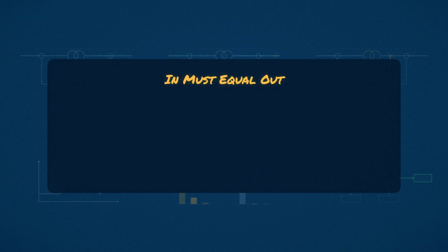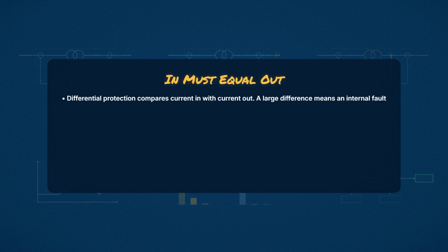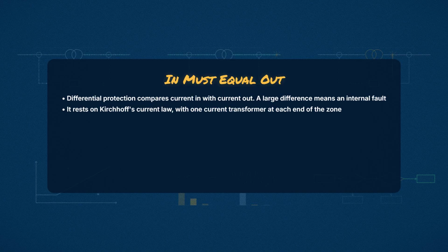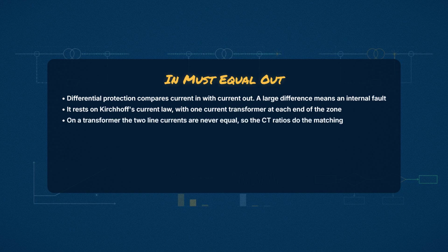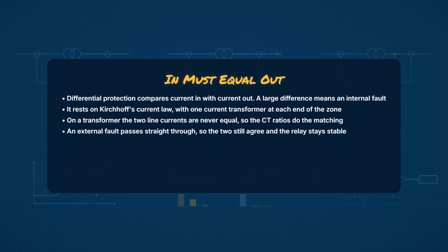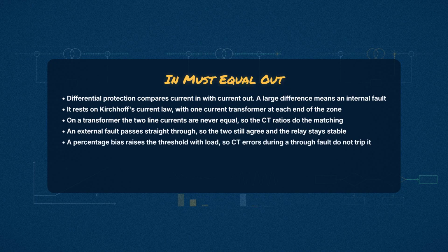So, a recap. Differential protection compares the current going in with the current coming out. A large difference means an internal fault. It rests on Kirchhoff's current law, using one current transformer at each end of the protected zone. On a transformer, the two line currents are never equal, so the current transformer ratios do the matching, and the relay compares what they hand it. An external fault passes through the zone, so the two still agree, and the relay stays stable. A percentage bias raises the trip threshold as the through current rises, so current transformer errors during a heavy external fault do not cause a false trip. And second harmonic restraint lets the relay ride through magnetizing inrush.